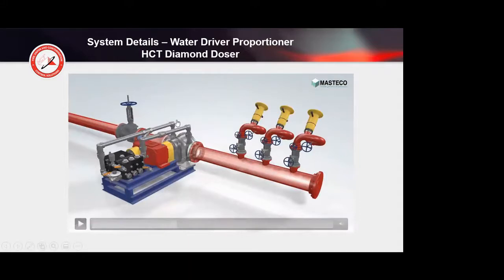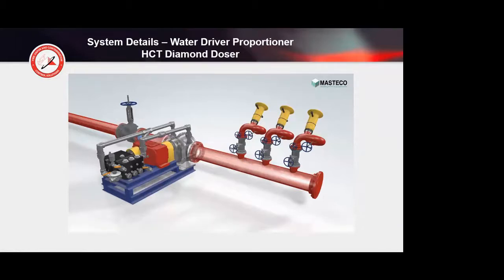So this part here is the water-driven proportioner that shows up at the job site. Ours is configured a little bit differently than this - I just use this animation to show it. Basically the contractor, the fire protection contractor, is cutting the pipe and putting flanges on. In our case, we can provide flanges or Victaulic couplings to connect to your existing piping.